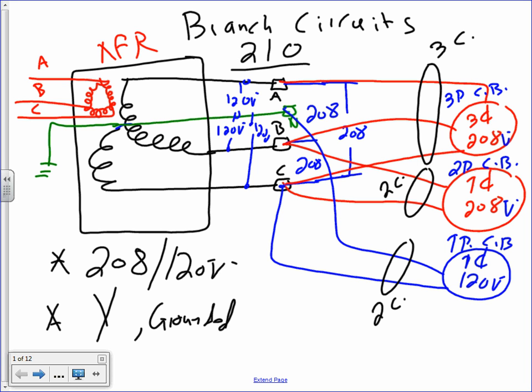Depends on what you take: when you take the 3 phases, you got 3-phase. You take 2 phases, any 2 phases, you got single-phase 208. If you got any phase and a neutral, what do you get? 120. Okay, I put 3-pole circuit breakers here, I put 2-pole circuit breakers here, and I put single-pole circuit breakers here. Everybody knows why? Every time you have a hot, what do you need? A pole for the circuit breaker. Any question about this diagram? And these are 3 conductors, these are 2 conductors, these are 2 conductors. Everybody can see the difference.